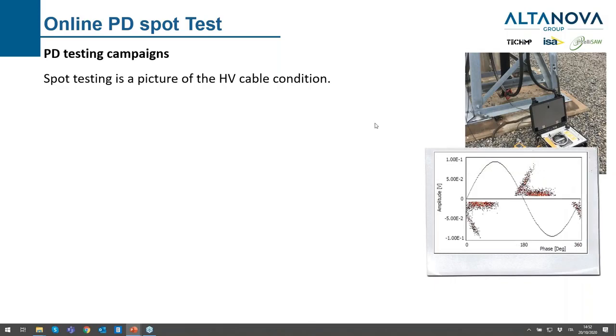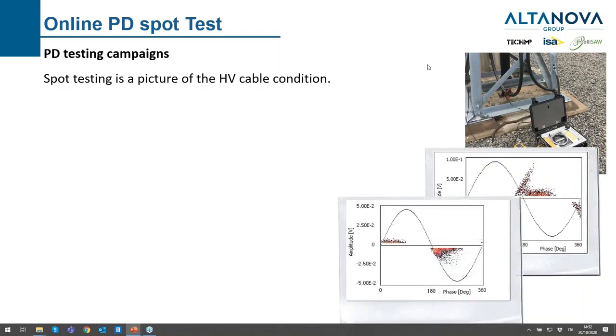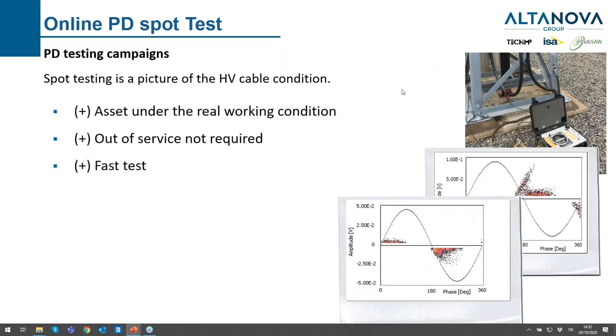We have to consider that spot testing is like a picture of the HV cable condition. There are several good points: the system works in real working conditions, so we have voltage, current, aging — everything is there. We don't need any out-of-service period. It's a very fast test because we can test three accessories in less than one hour, for example if you have a skid operator on site.